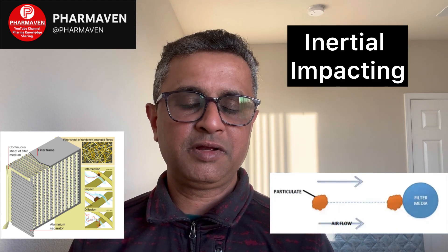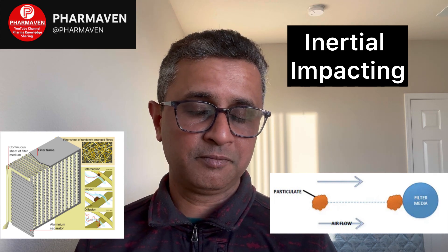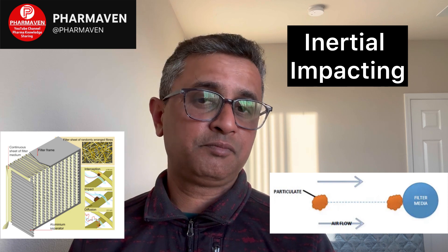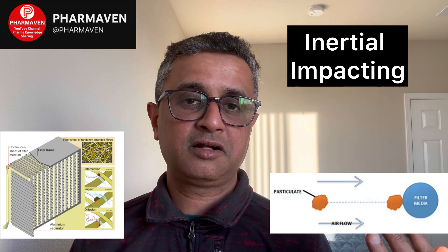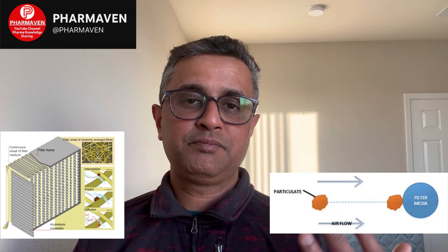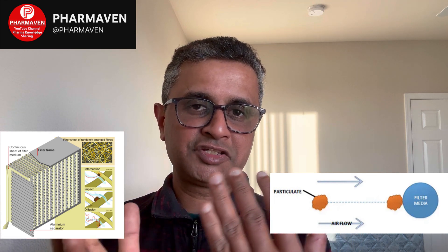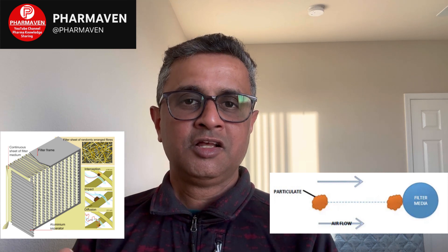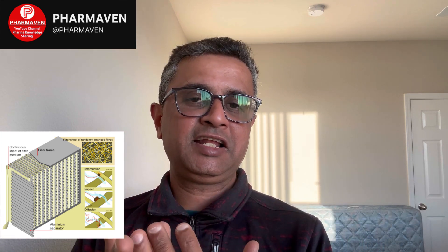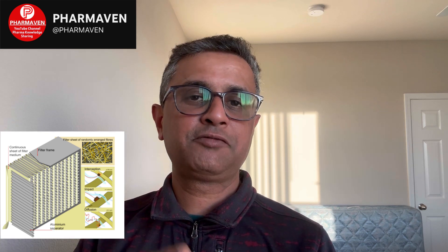The second mechanism is inertial impaction. When particles around 0.3 micron travel through the air at a certain velocity and impact the structure of the HEPA filter, they attach to the fibers because of that impact. Due to the velocity and impact, they get attached to the fibrous structure and do not pass beyond it — they get entrapped within the filter.